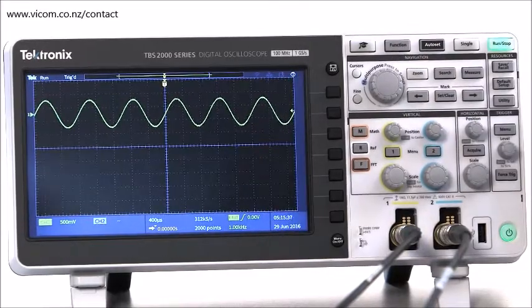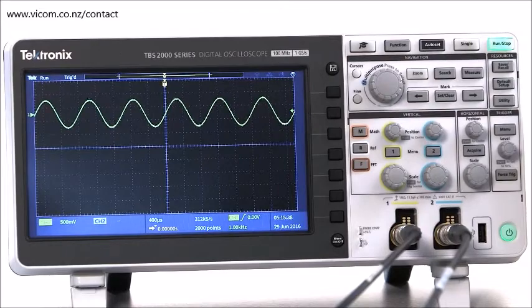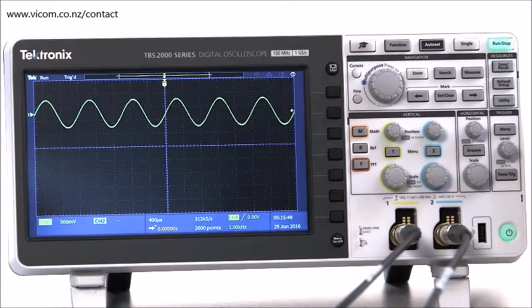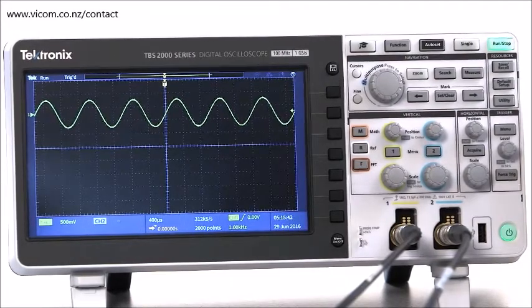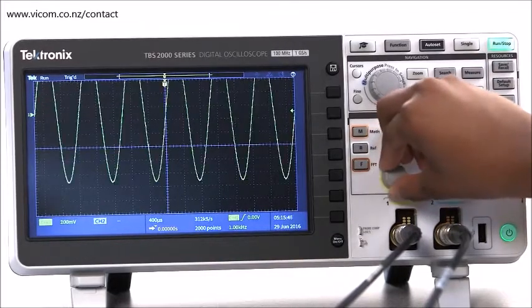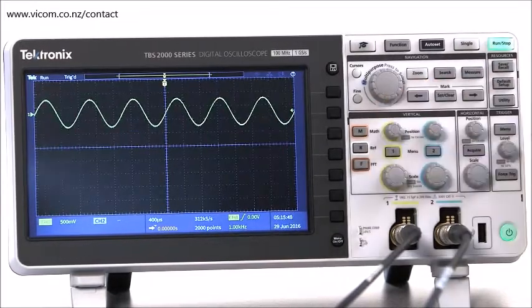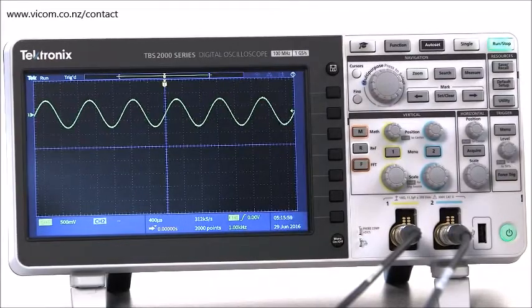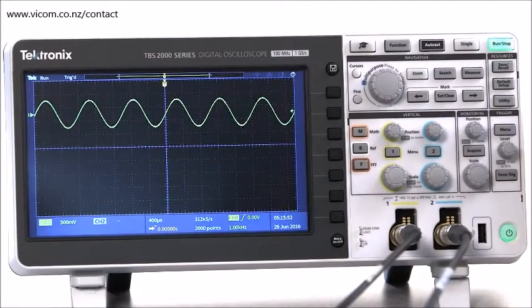The vertical controls configure the y-axis of the display, which is usually, but not always, represented in volts. The vertical scale appears to make waveforms taller or shorter, but in actuality, it determines how many volts are in each vertical division of the screen.